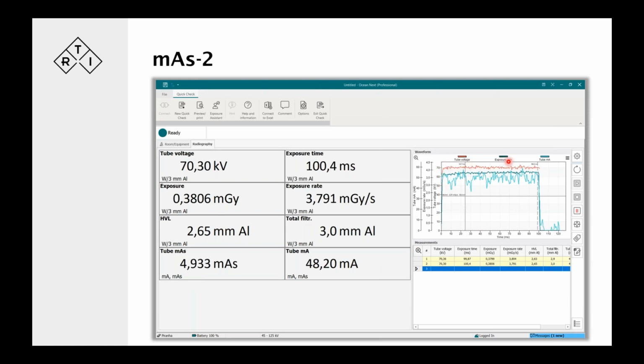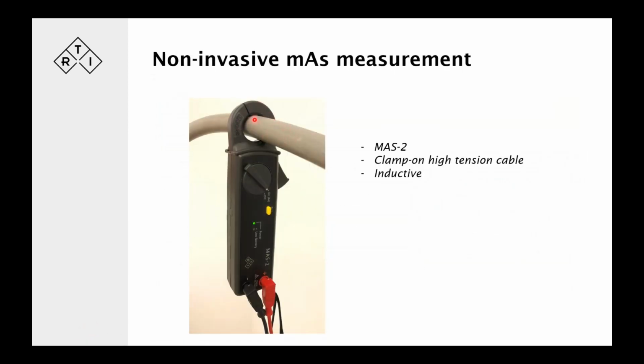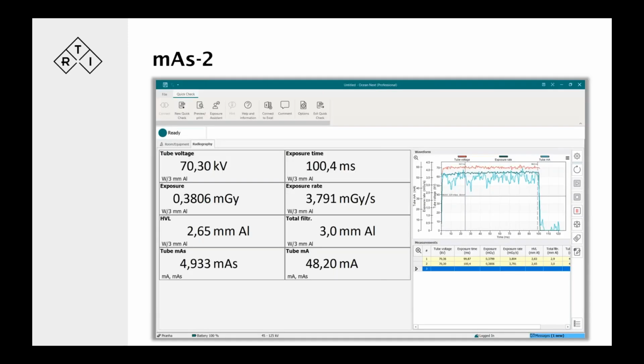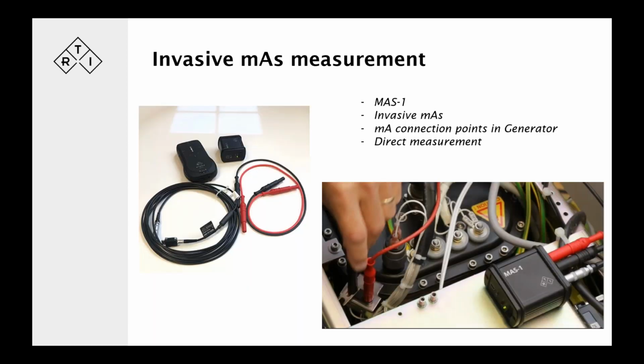In the waveform window, we've got the kV, we've got dose rate, and we've got mA signals, so that we can analyze to see if there is something that needs to be done or something that looks strange as we move along. So it is quite an easy thing. All we need to do is clamp it on to the high tension cable, and off we go and get a decent value for the mAs values. Of course, there are limitations to what we can pick out inductively from a cable, which includes shielding. So for some precise measurements, the invasive measurement is to be recommended.